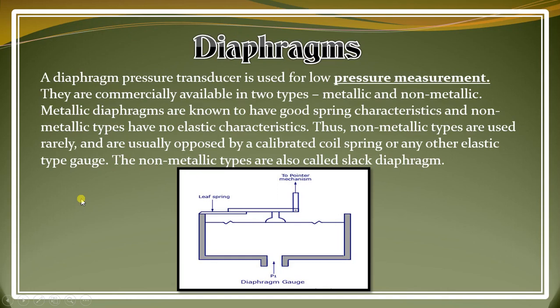So what are elastic diaphragms? Actually, the diaphragm is an elastic device, or it can be a metallic device also. When we apply a pressure, it deforms, and its deformation is directly proportional to the applied pressure. So it can be metallic or non-metallic. In the metallic type, the metallic diaphragm has a spring quality. When we apply pressure, the metal deforms, and when we remove the pressure, the metal gets back its original shape. If it is non-metallic, it can be elastic when we stretch it and when we release it. You can understand it by this.